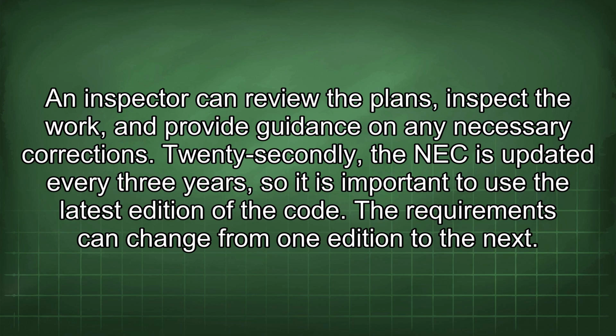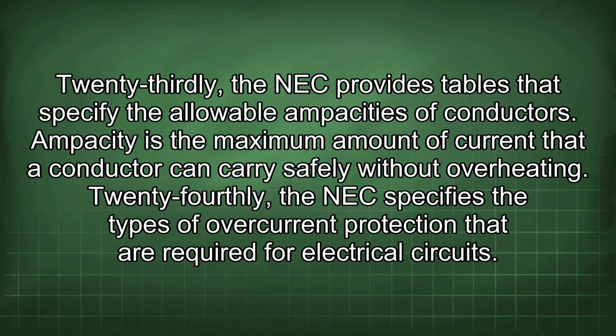22ndly, the NEC is updated every 3 years, so it is important to use the latest edition of the code. The requirements can change from one edition to the next. 23rdly, the NEC provides tables that specify the allowable ampacities of conductors. Ampacity is the maximum amount of current that a conductor can carry safely without overheating.